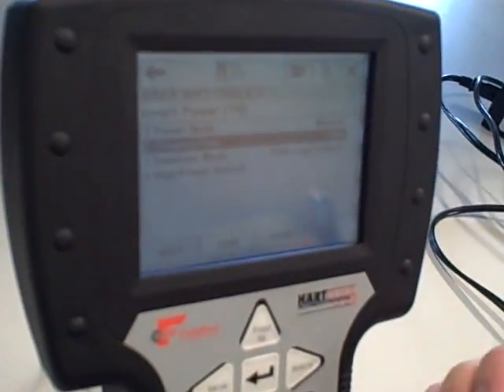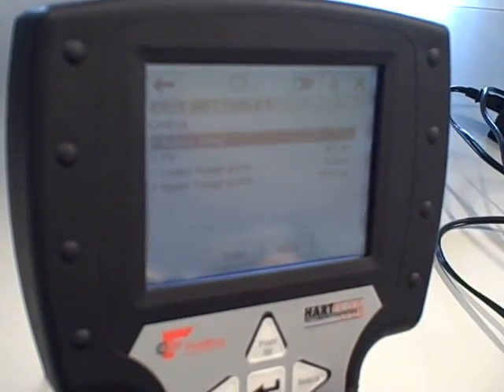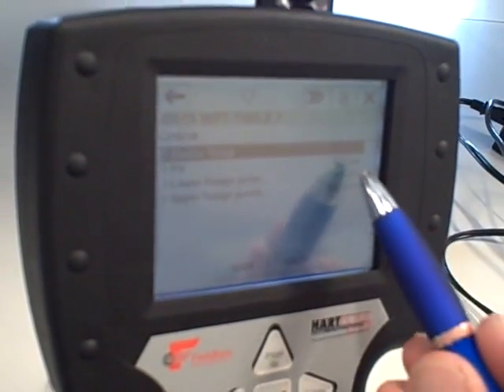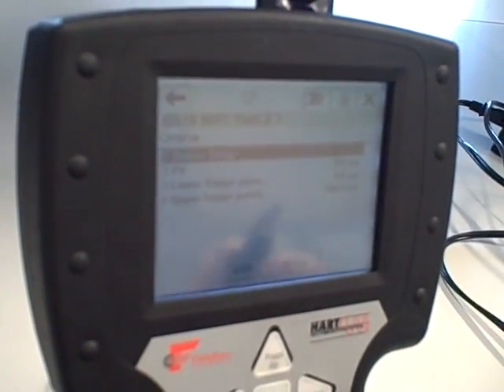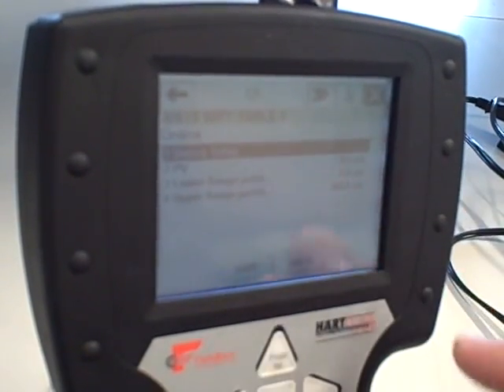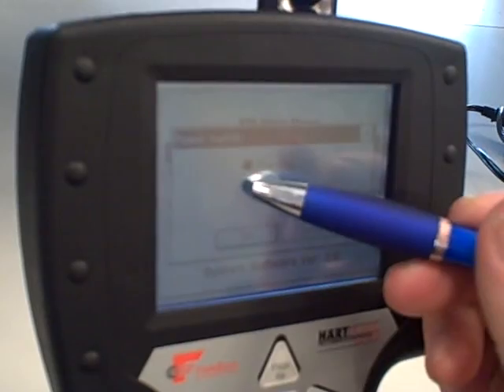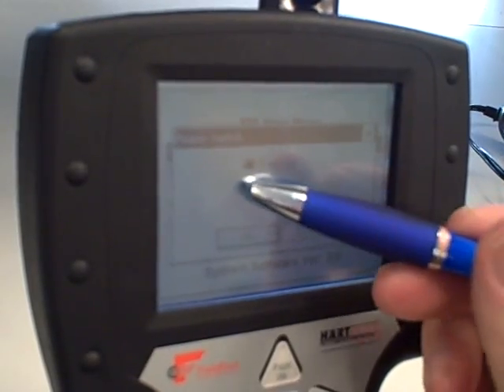At this point, I can navigate out of the menu structure. I can go back to its home page, where it shows it's reading zero psi, and I can exit out of this and turn the power off for the HART communicator. And yes, I do want to shut down. There we go.